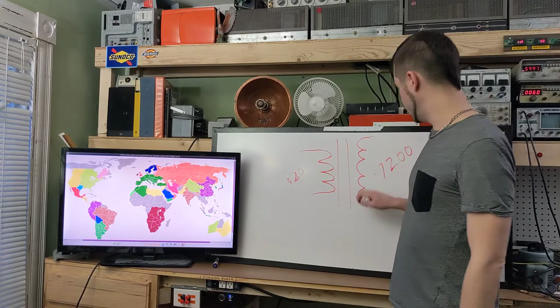The transformer enabled the use of high voltage, and high voltage allows you to transmit power with very low losses, because what determines how much electricity is lost on a wire is the amperage, or current, not the voltage. So the higher the voltage, the lower the amperage for a given amount of power, and you have less loss. It's actually a very dramatic effect - the power loss goes down with the square of the voltage. So if you double the voltage, your power loss goes down by a factor of 4.